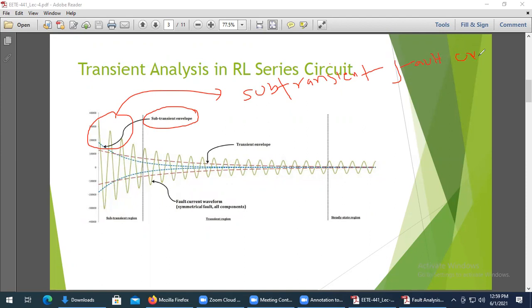Now, if you take a closer look at the exponential component again, it is decaying over time, as a function of T. This is the DC component here, which I can separately draw like this. You see, with the increase of time, as the fault current keeps flowing and time elapses, the magnitude of the DC component reduces, and so does the magnitude of the total fault current, because the total fault current is always the summation of the AC component, or oscillatory component, plus the DC component.